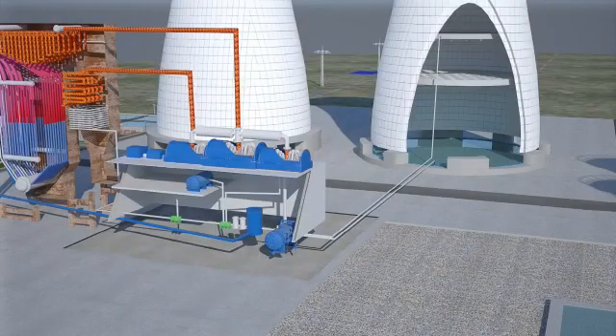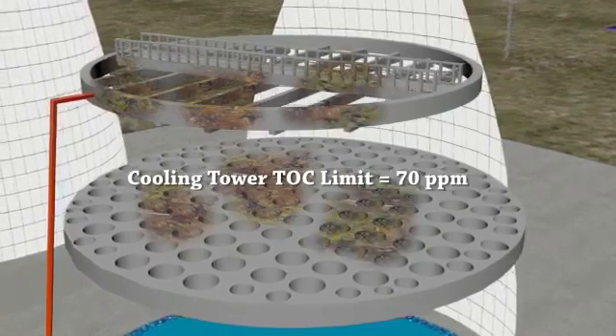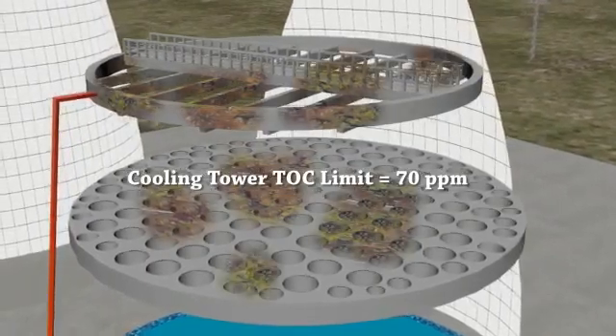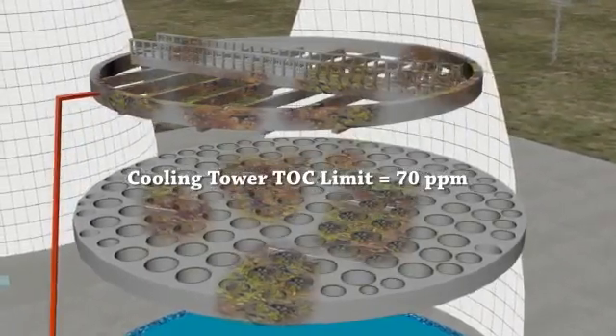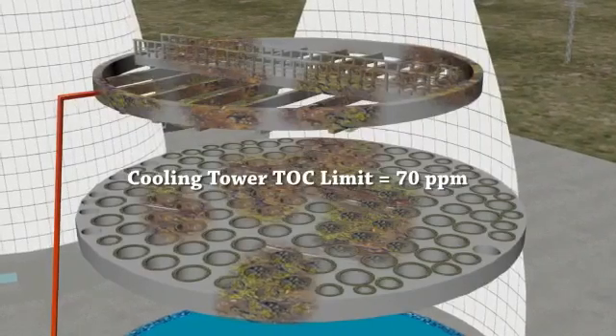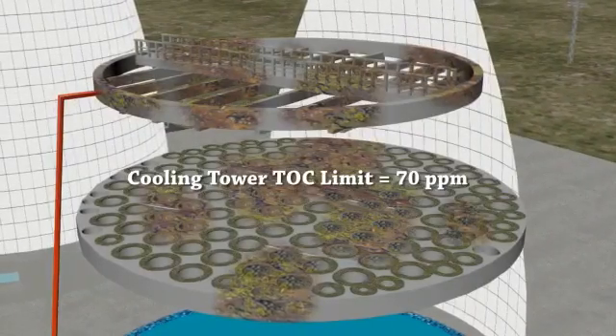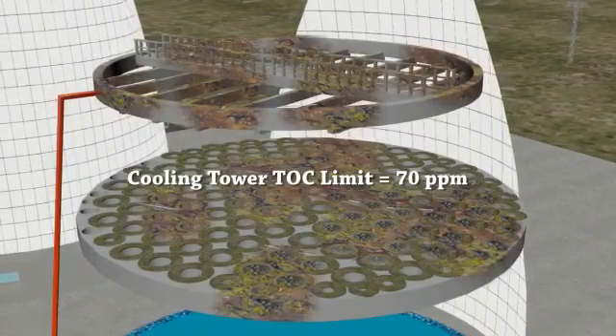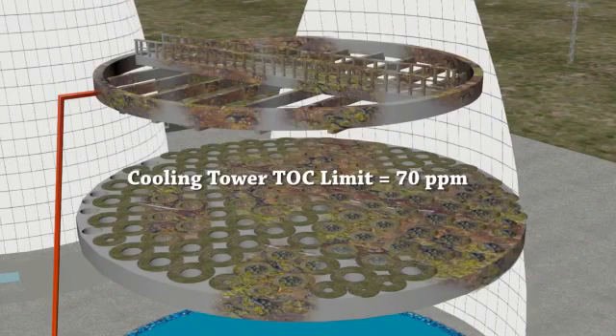The level of TOC builds up with each cooling cycle. The general discard limit of cooling water using TOC is 70 ppm. After this limit, TOC in the water will damage the cooling tower and condenser quickly. Hence, timely monitoring and blowdown is advised for cost efficiency.